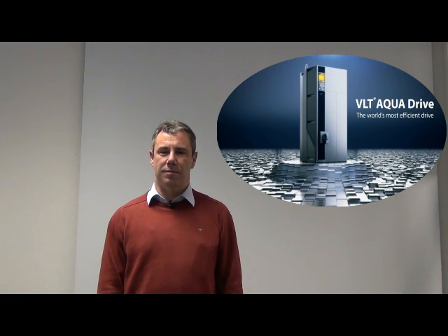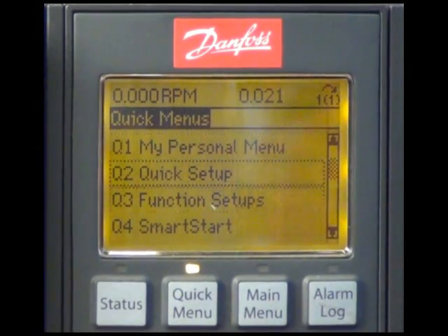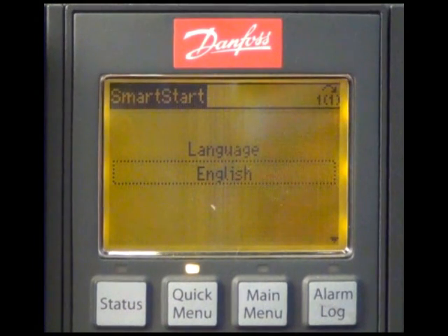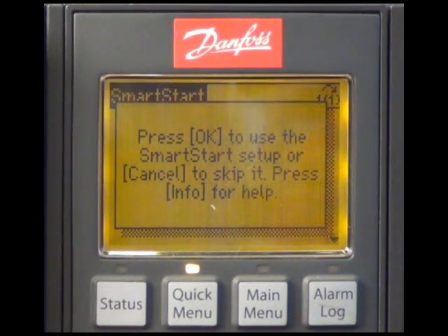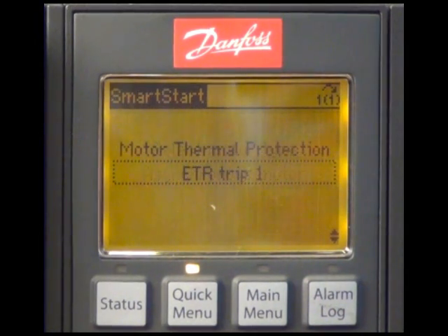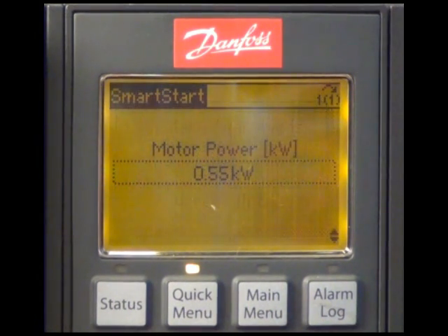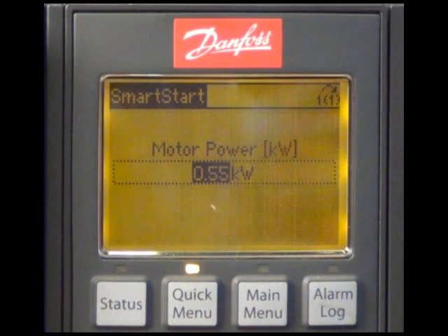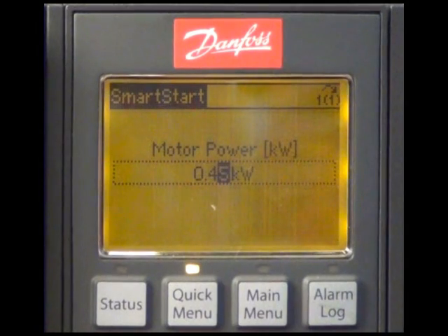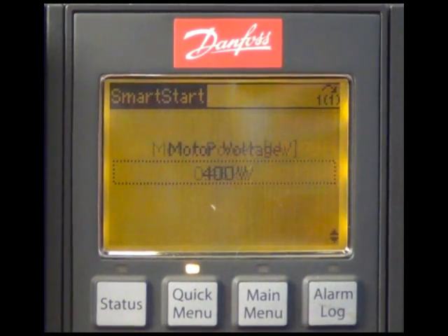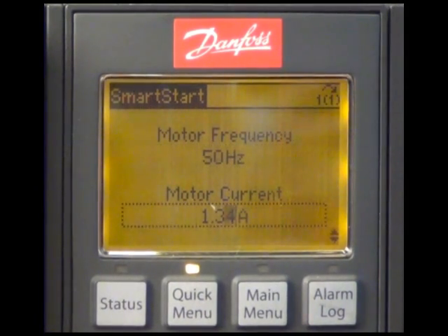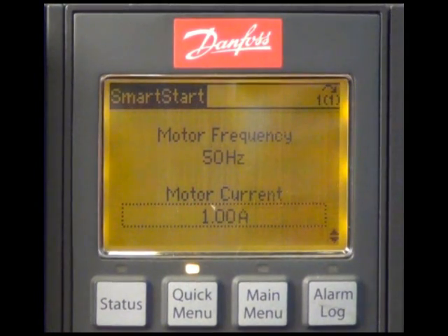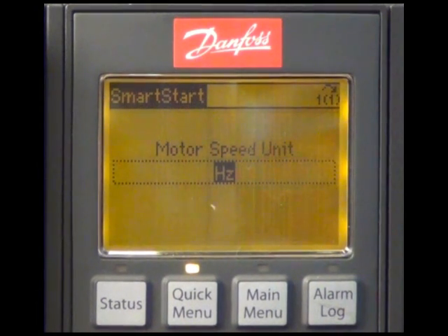Now I will program the follower. I will enter the SmartStart again by the entry in the quick menu. As you will see, most of the settings, at least of the basic settings, are exactly the same as for the master drive. We have to enter again the motor data and because they are the same for the master and the follower we are using of course the same settings. Again, hertz as motor speed unit.